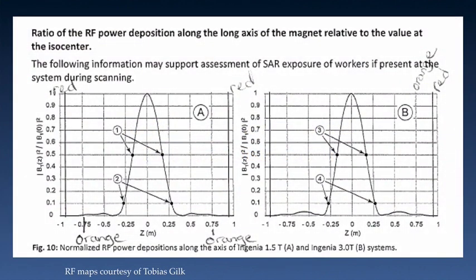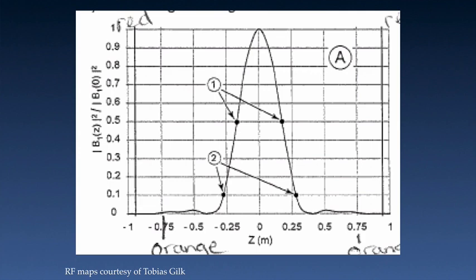Here is a sample map from both a 1.5T and 3T Philips Ingenia system, courtesy of Toby Gilk. Since they are the same, we're going to zoom in on the 1.5 Tesla map. The horizontal axis represents the z-axis or head-to-foot axis of the magnet, so zero is isocenter.